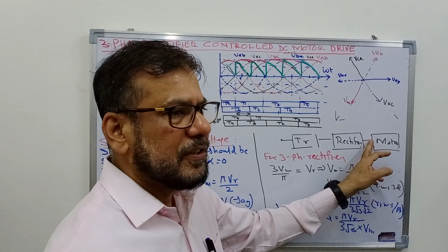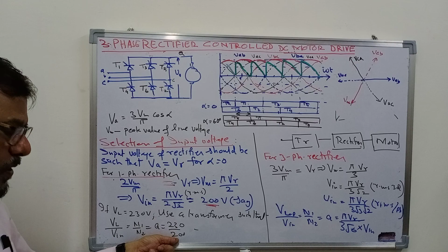So you have to use a step down transformer. If this voltage was 300 volts, then you would have to use a step up transformer, so that for alpha equal to 0, the voltage reaching here equals the rated voltage of the motor. Suppose VL is 230 volts, the available line voltage, then you have to use a transformer such that VL upon Vin equals N1 upon N2, that is the turn ratio of the transformer should equal 230 upon 200. This is the turn ratio of the required transformer.